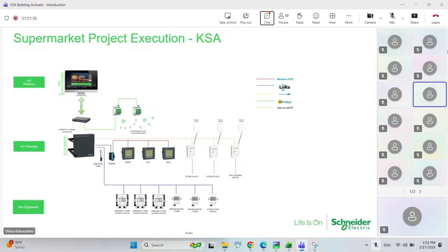So with our architecture, especially with SE8000s, and of course adding more use cases, like Dina told about metering and long-range sensors, especially wireless sensors for display chillers and freezers which are far away from where the gateway was, all put together, it became a very strong use case. We again drove 14 to 15% savings on the utility bill here. It's good to know that it's a 24-hour supermarket chain, a convenience store that you find in petrol stations. But despite that, we could drive good savings at this site as well. So again, simplified architecture, multiple use cases, and a focus on reducing the utility cost.